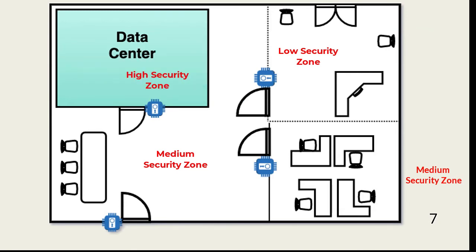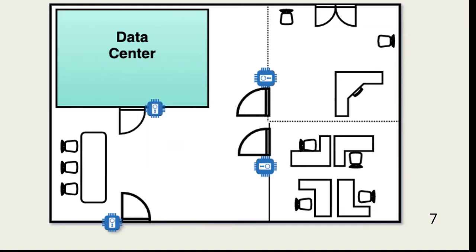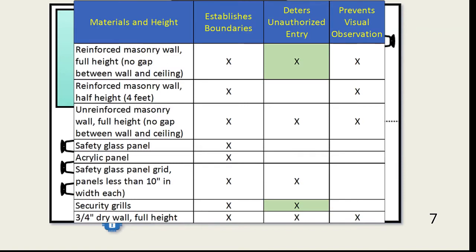The data center is a high security zone. Note that the data center wall is not shared with the external structure wall. If a data center is located on the ground floor, it should never share an external wall with a structure. Internal wall construction is important when looking at deterrence and prevention. Walls enclosing a high security area should not also form part of a building's exterior wall.